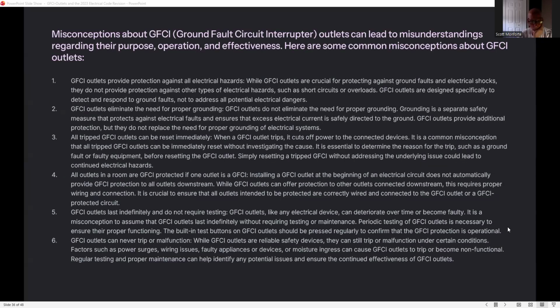All right, here's a big one. Misconceptions about GFCI outlets can lead to misunderstandings regarding their purpose, operation, and effectiveness. Here are some misconceptions about GFCI outlets. Number one, GFCI outlets provide protection against all electrical hazards. While GFCI outlets are crucial for protecting against ground faults, they do not provide protection against other types of electrical hazards, such as short circuits or overloads. GFCI outlets are designed specifically to detect and respond to ground faults, not to address all potential electrical dangers.